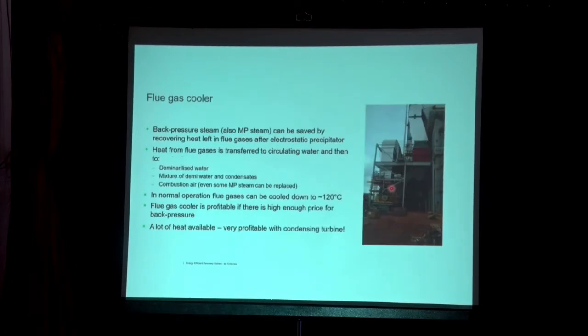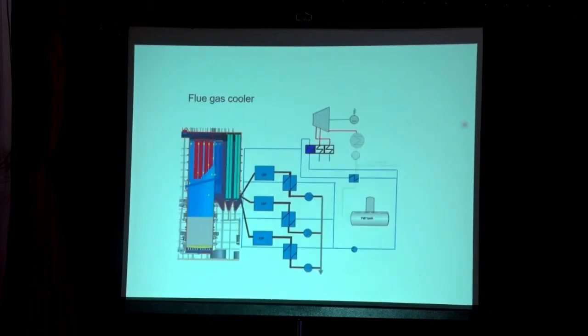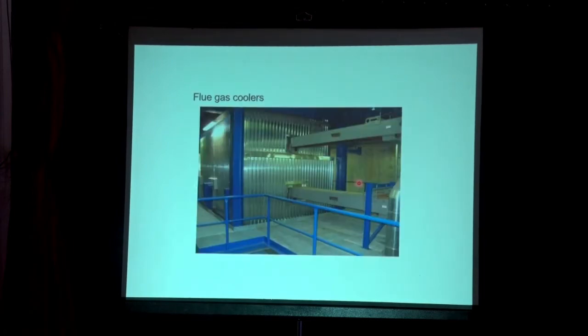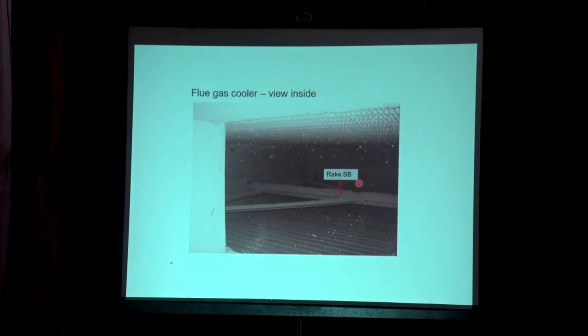For flue gas coolers, they are installed after the electrostatic precipitator at the outlet. Circulation water is heated by the flue gas, and that water is used to heat demi-water and combustion air. Rake-type soot blowers are used for cleaning the flue gas cooler.